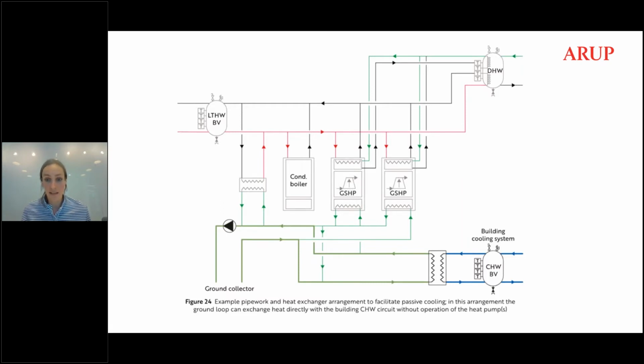The designer of this system really should understand what the trigger points are. When should this turn on? When should it turn off? How do we know how much heat is stored at any one time in the thermal store? When should it be discharged? How much heat is being transferred to and from a ground system?